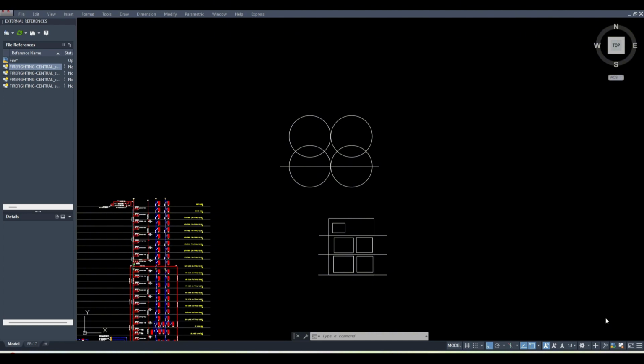Okay. Then the distance between the two sprinklers, you cannot keep it more than 4.5 meter. Or in the best case we are using 4 meter, even 0.5 meter we are reducing so that we can cover these dead end areas, the uncovered areas. So the best practice is we keep the gaps at half of the sprinkler spacing, and the sprinkler to sprinkler distance we keep 4 meter. Okay, so is it clear?